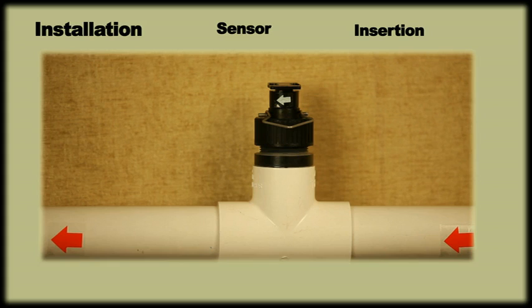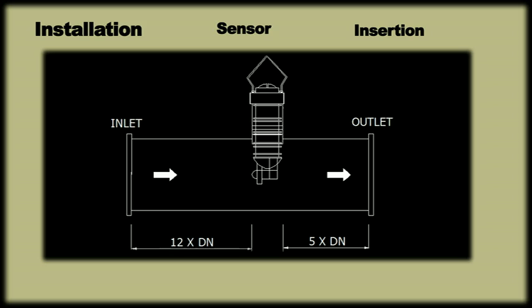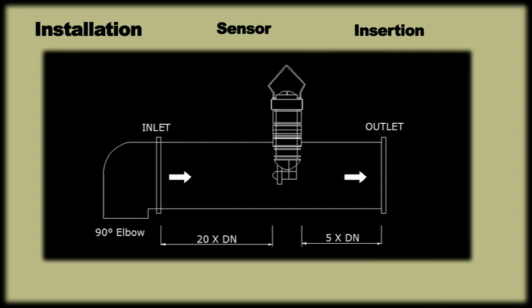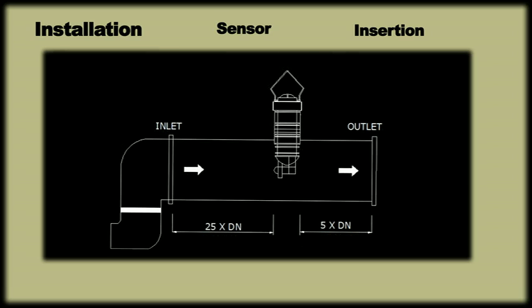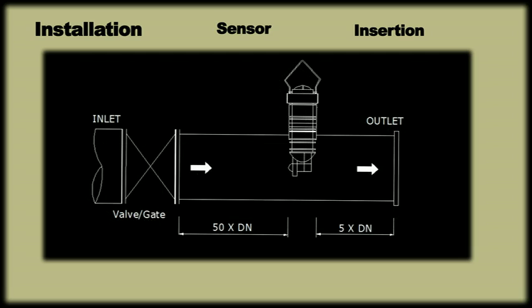Maintain a minimum inlet straight pipe length as per the following guidelines: 12 times pipe diameter in case of straight run, 15 times pipe diameter in case of reducer, 20 times pipe diameter in case of 90 degree elbow, 25 times pipe diameter in case of two 90 degree elbows, 40 times pipe diameter in case of elbows in different plane, 50 times pipe diameter in case of gate or globe valve. The minimum outlet pipe straight length must be 5 times the pipe diameter in all cases.